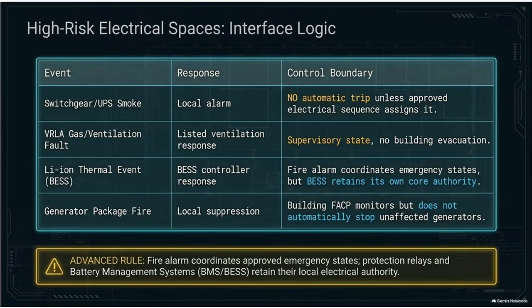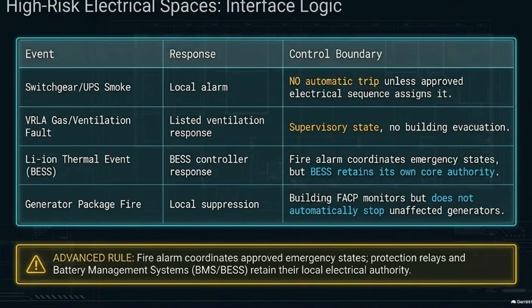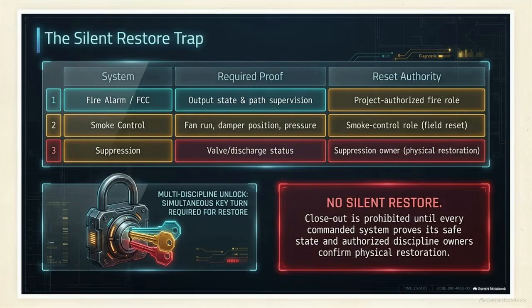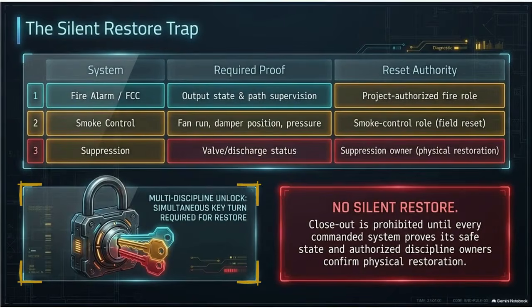This interface table addresses high-risk electrical spaces requiring distinct logic. Lithium-ion battery and generator packages present unique thermal challenges. The advanced rule applies. Main fire alarms coordinate emergency states, but local battery controllers and relays retain core authority over their systems. This chart highlights the silent restore trap. You cannot hit reset if physical hardware is still actuated. It requires a multidiscipline unlock. Closeout is prohibited until authorized owners confirm valves, dampers, and fans are physically restored to safe, normal states.